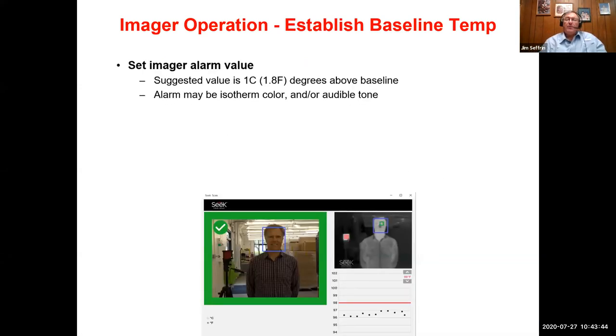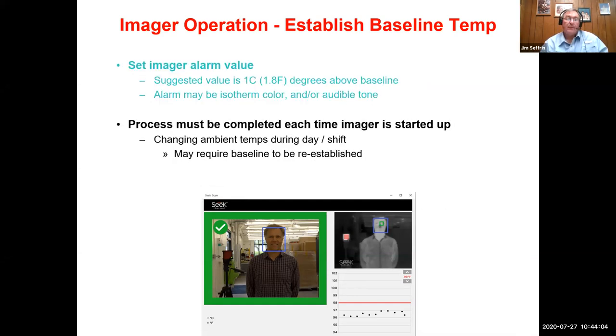Once you've established your baseline temperature value, you then set your imager alarm value. The suggested value is 1 Celsius degree or 1.8 Fahrenheit degrees above your baseline. That alarm may be isotherm, it could be a color or an audible tone. Any of these are acceptable.